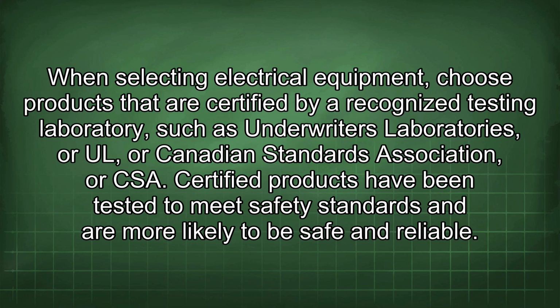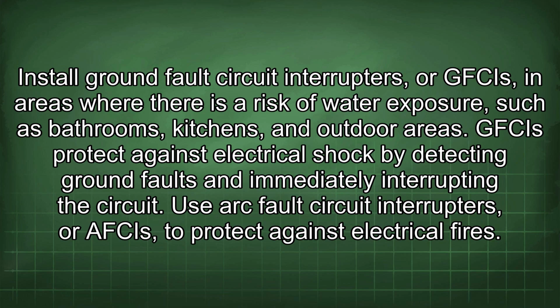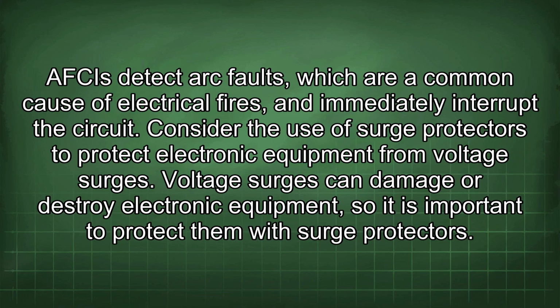Certified products have been tested to meet safety standards and are more likely to be safe and reliable. Install ground fault circuit interrupters, or GFCIs, in areas where there is a risk of water exposure, such as bathrooms, kitchens, and outdoor areas. GFCIs protect against electrical shock by detecting ground faults and immediately interrupting the circuit. Use arc fault circuit interrupters, or AFCIs, to protect against electrical fires. AFCIs detect arc faults, which are a common cause of electrical fires, and immediately interrupt the circuit.